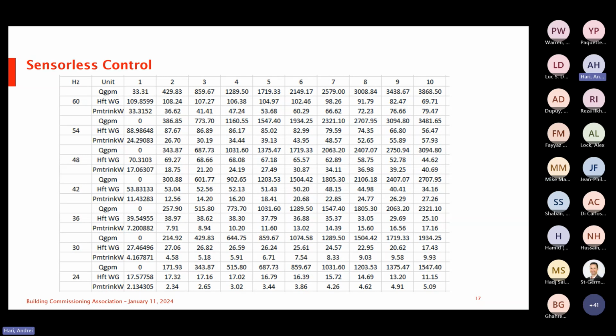No and no. The way this is done is that at the factory, we have a calibrated flow meter on the test rig. So the data points come directly from a calibrated flow meter in the factory. The end result is that the accuracy is within 3 to 5%, just like the calibrated meter. And simply because of our industry, we're typically moving water or glycol in our system, so we don't see wear on the impeller or the volute over time that would degrade the data points in the system.